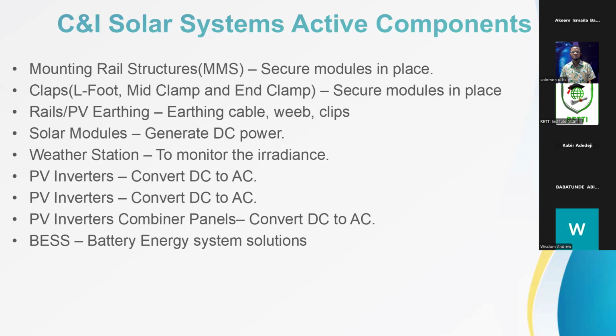Some people call it a battery inverter, some people call it PCS, right? If you look at the 200 for Huawei, they have connected everything for you internally. What you need is your output, which is line, neutral, red, yellow, and blue, and your what? Neutral and earthing. Mind you, for the 200 Huawei, it doesn't have a neutral.